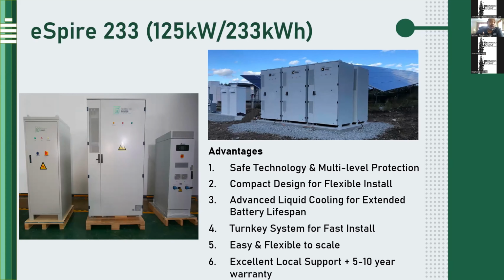We look at the power, and literally it's just math. If someone has 100 kW, for easy math, and you want to back it up for 6 hours, then you need 600 kWh of storage, that's how the math works. The eSpire solution is 125 kW of power. This cabinet is 233 kWh of storage, and then you have our control panel.